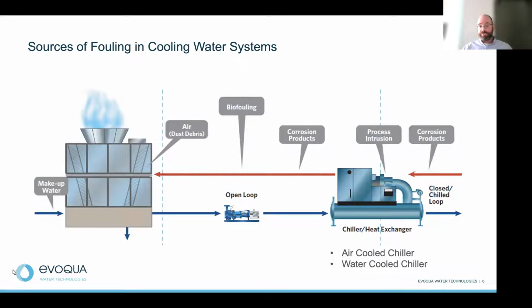You may have multiple chillers or multiple heat exchangers, and maybe they're not always all operating. So you may have some areas of stagnant water or low flow, in which case bacteria can grow, corrosion can happen. You may have an intricate piping system and there's dead legs in there, again, where corrosion and biofilms can form and start to cause some really troublesome fouling issues. So it's a very, very dynamic system, and that's where fouling can come from.